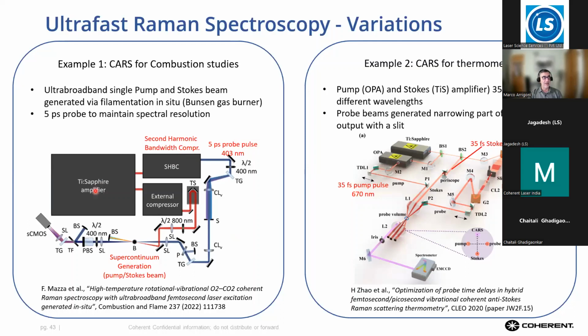This is an interesting setup where the femtosecond laser is used to generate a super continuum very close to the sample. In this case it's a combusted gas. Both the pump and the Stokes are femtosecond, very broad bandwidth, and the probe pulse at 400 nanometers is instead in the picosecond regime, guaranteeing the resolution.